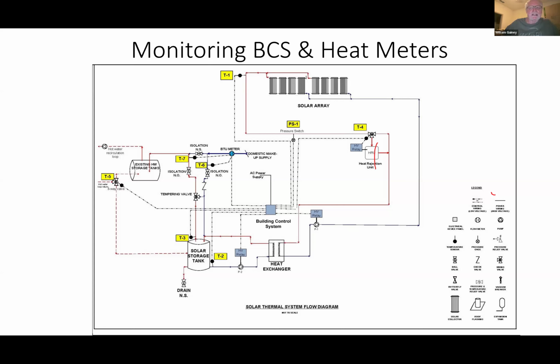But in reality, what we can do is provide the exact energy we're producing to a facility, and we can either do a sale of energy project, we can do a shared savings project, and all of those energy consumption data can be used to validate the amount of energy produced by the solar heating system. So integrating a solar thermal system into a building control system is pretty easy to do. And many of the manufacturers have equipment that can tie into a building control system. Their differential controller and sensors can tie directly into a building control system. And most of the manufacturers of controllers and solar thermal systems have that technology available to them.